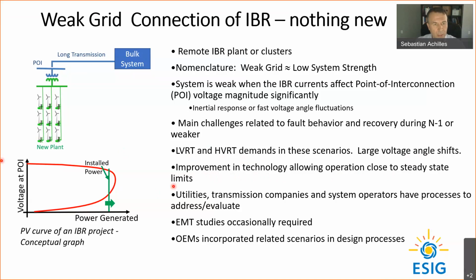Referring to this graph in the lower left, this shows the voltage at the POI and the power generated - a typical PV curve. The red curve is the performance of the system; there's a steady state limit beyond which we cannot push more power from this plant than what is tolerated or demonstrated by the red curve. The technology of inverter-based resources has progressed such that we're able to get very close to the nose of these curves for the weakest conditions of the system.